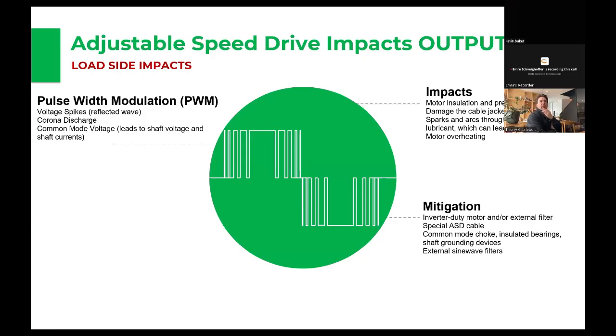So we did have an answer here from Kevin Baker. Not as such. The VFD is a soft starter by the fact that it controls both voltage and current to the motor. The output waveform doesn't bear on the soft start function. Right. So if the question has to do with the soft starting function of the VFD, then yeah, Kevin's correct. It has no bearing on the ability to just magnetize your motor and bring it to speed without any inrush current. So that's not an issue at all.